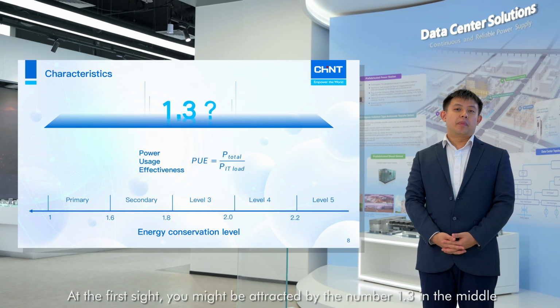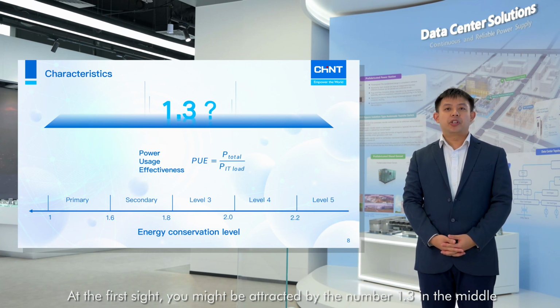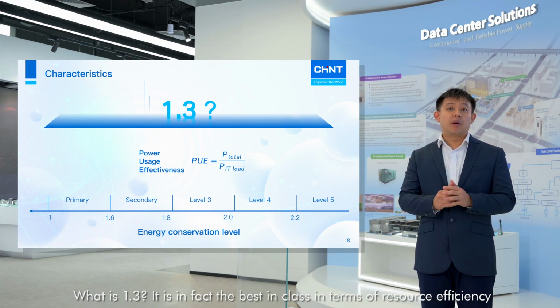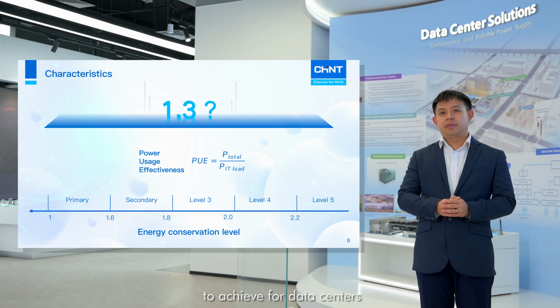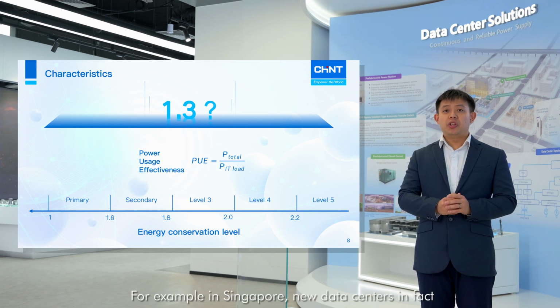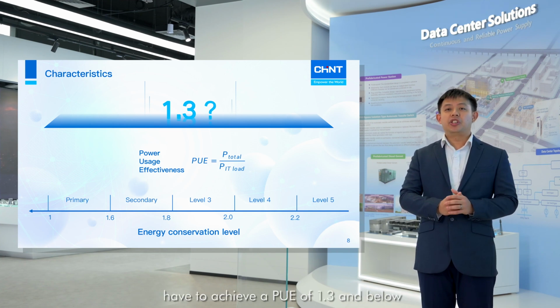At first sight, you might be attracted by the number 1.3 in the middle. What is 1.3? It is in fact the best in class in terms of resource efficiency to achieve for a data center. For example, in Singapore, new data centers in fact have to achieve a PUE of 1.3 and below.